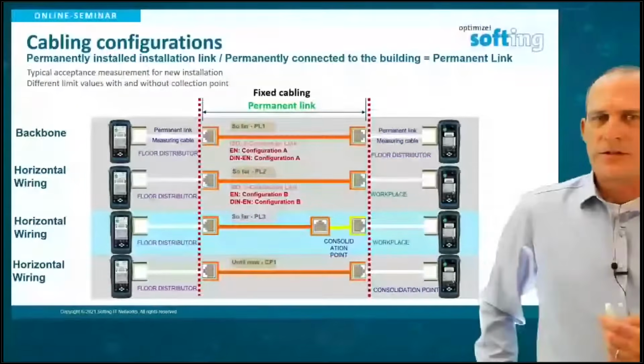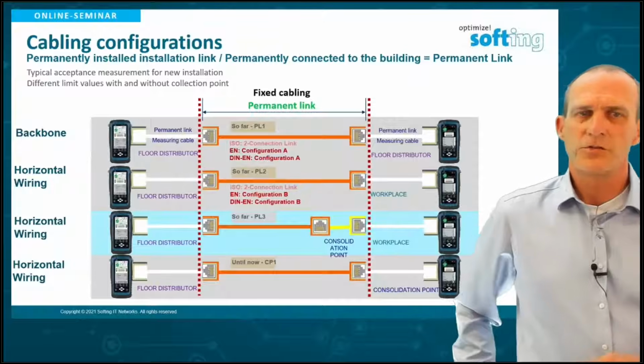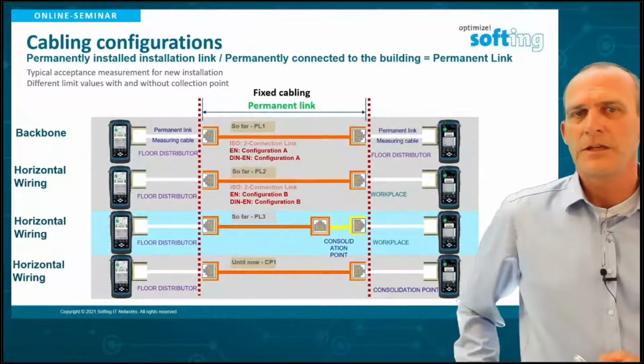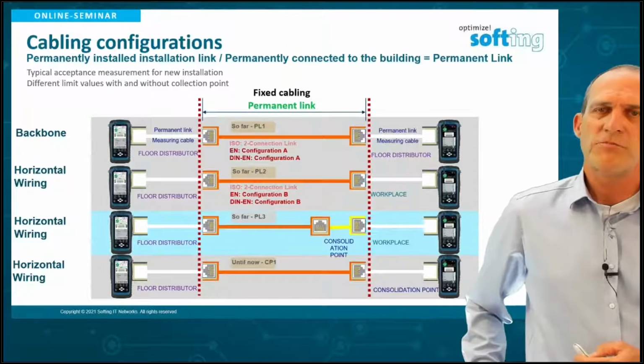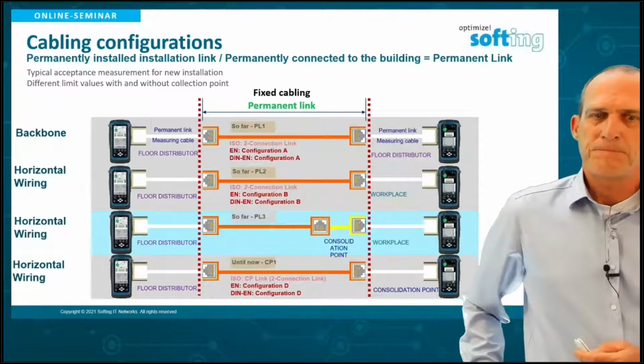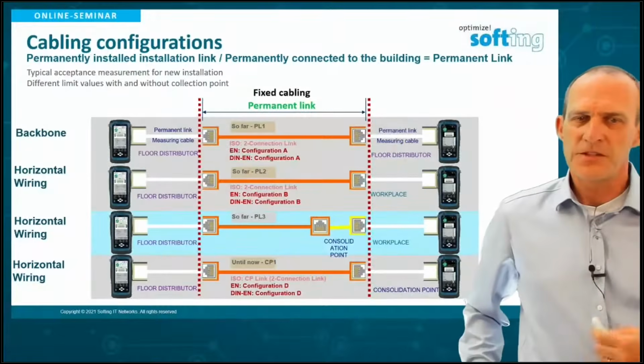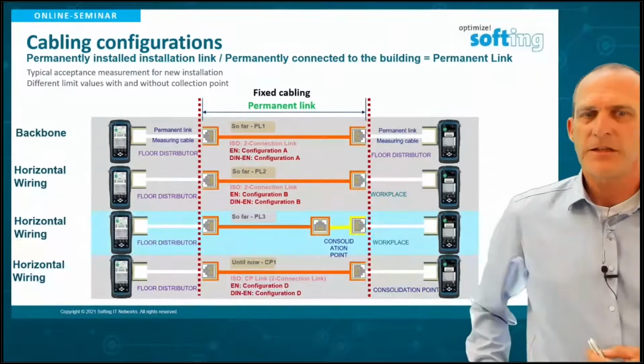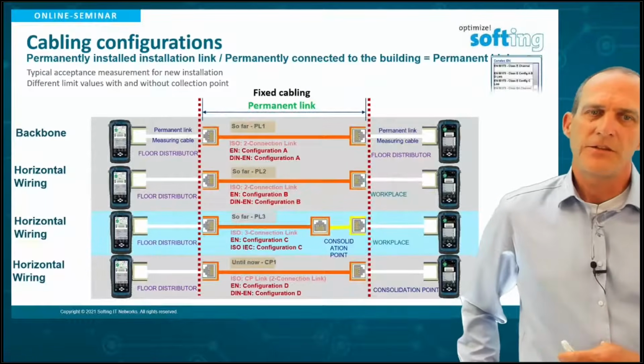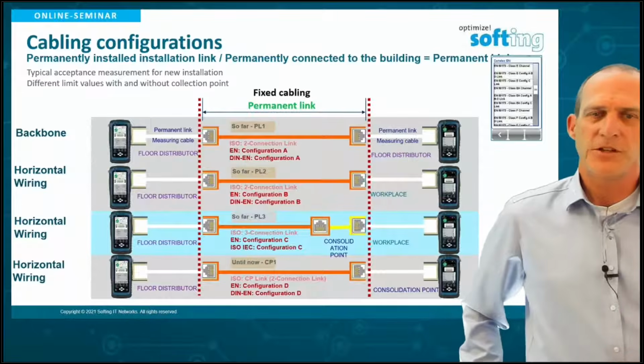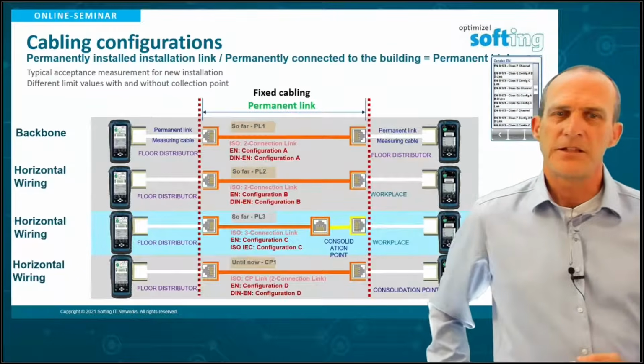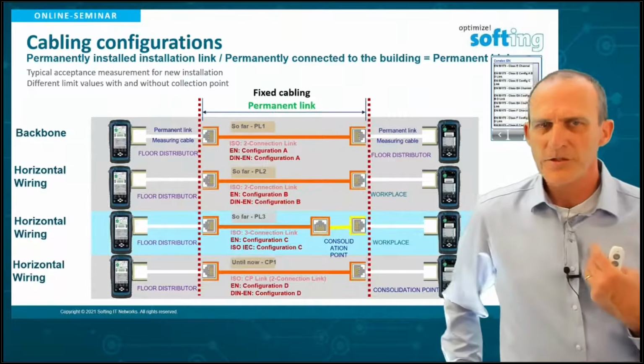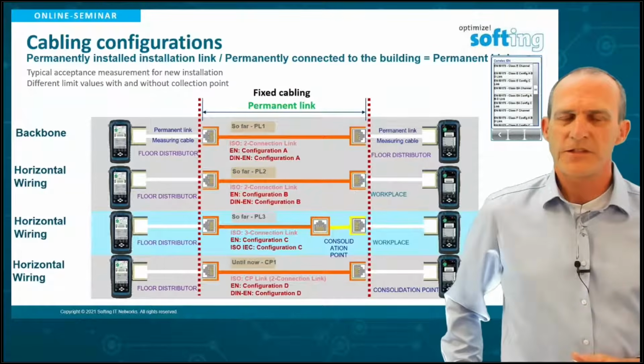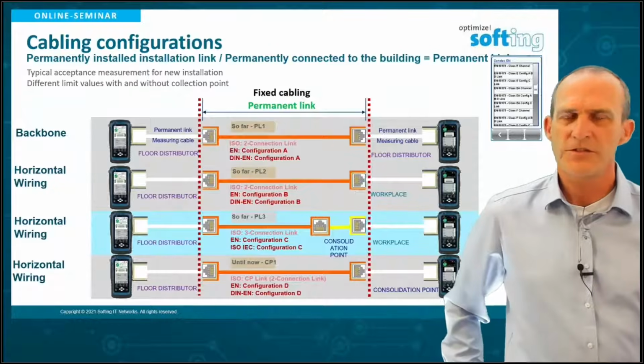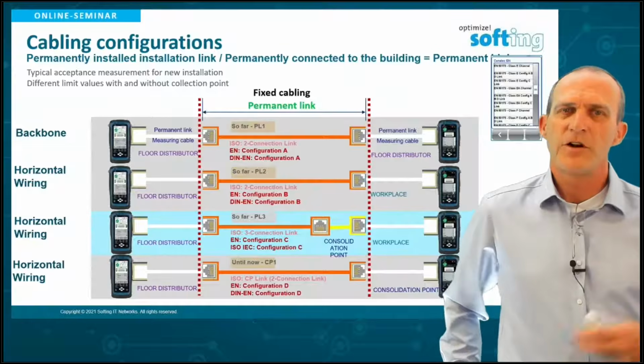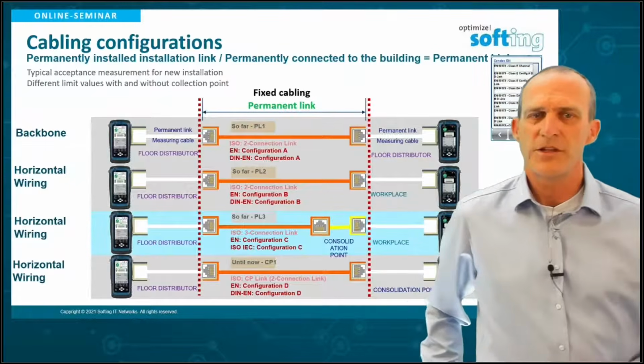PL2 in the ISO world is also called a 2-connection link; in EN it's called configuration B. The CP link is now also a 2-connection link, configuration D in EN. And the one with three connections is now called the 3-connection link in ISO, and configuration C in EN. I personally prefer the ISO naming because it's more obvious - 2-connection, 3-connection. The EN approach is more formal, using configuration A to D.